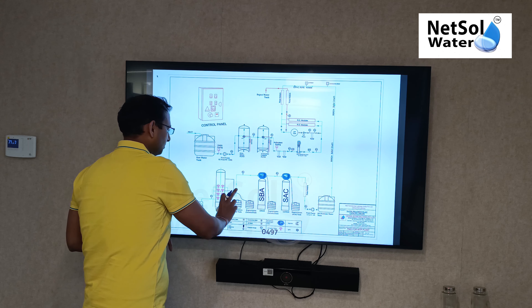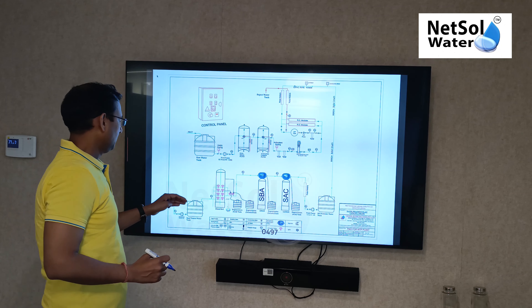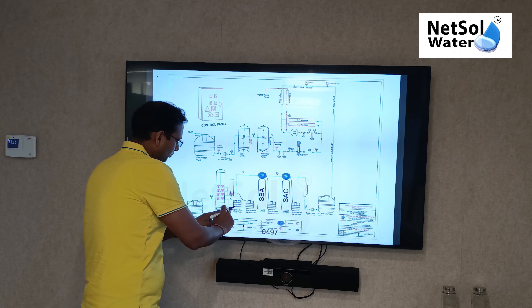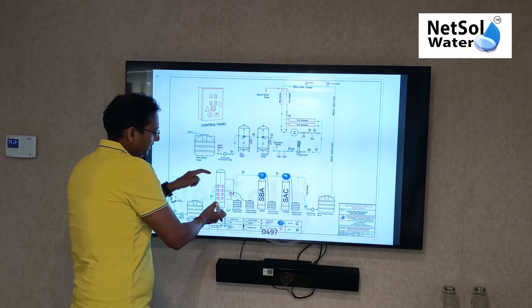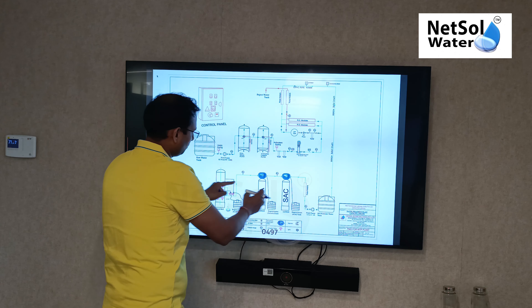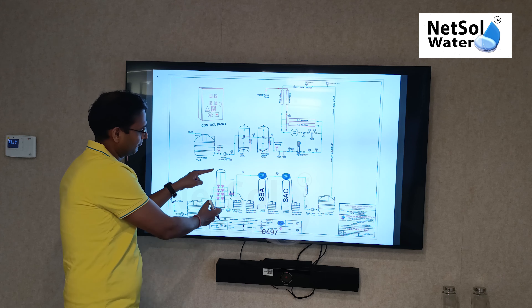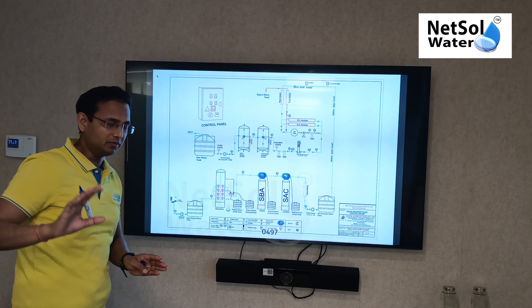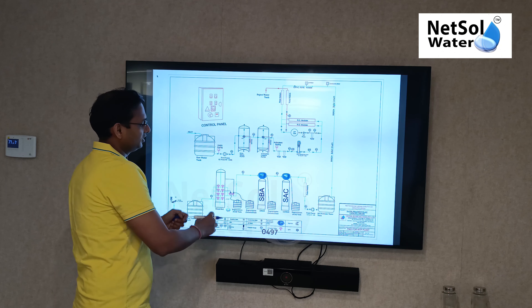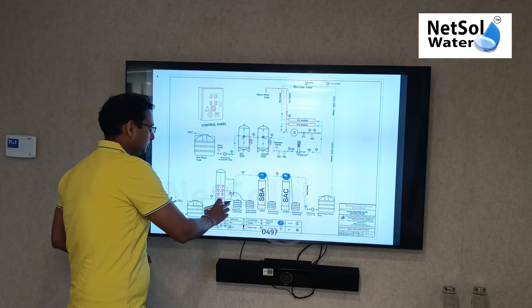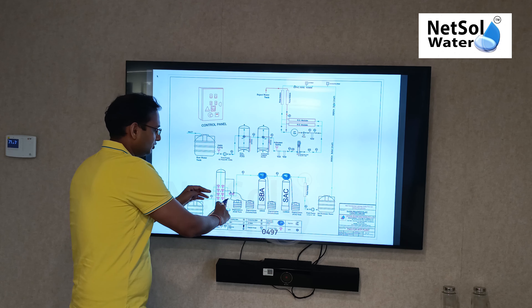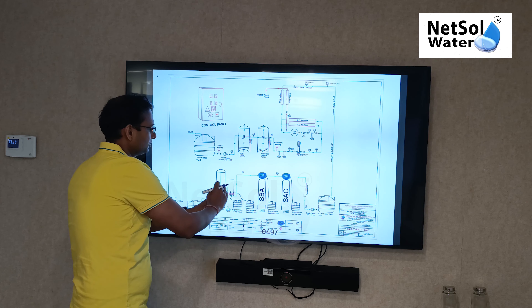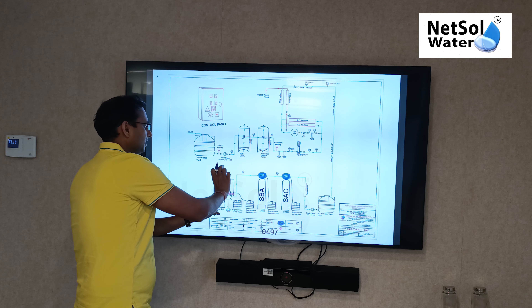Here TDS is coming down to 10 to 15, but because we need zero TDS, we add a mixed bed plant. In the mixed bed plant, we add both cation and anion resin together, and then we add a blower. This entire process is happening in one plant, in one vessel.